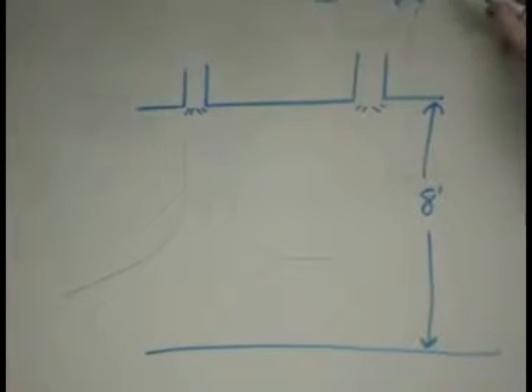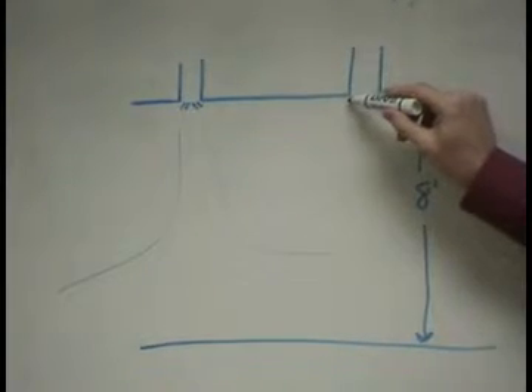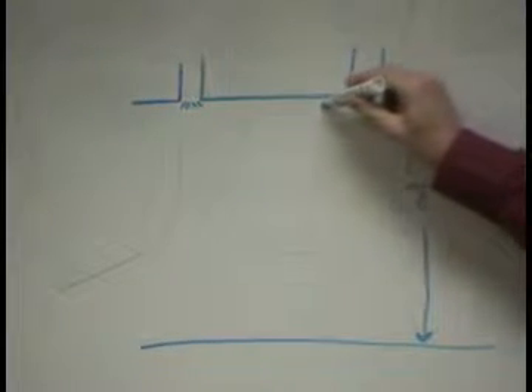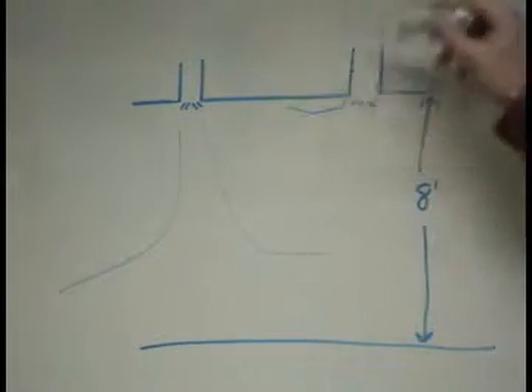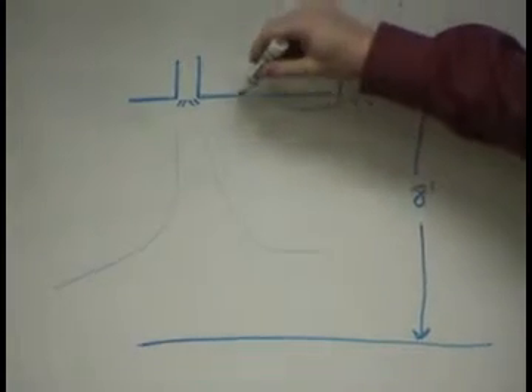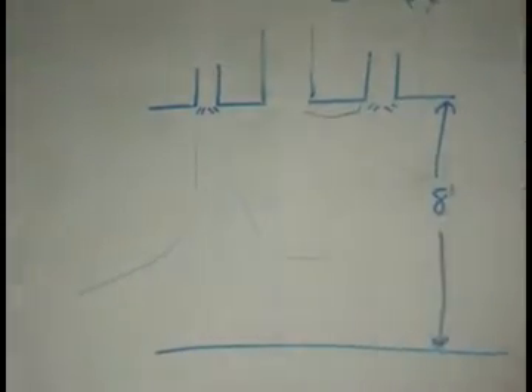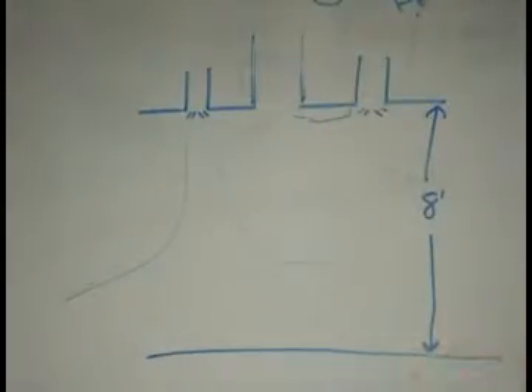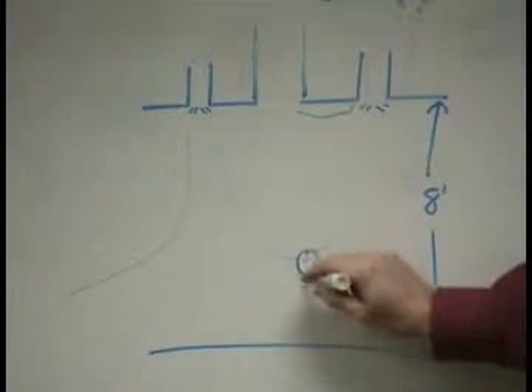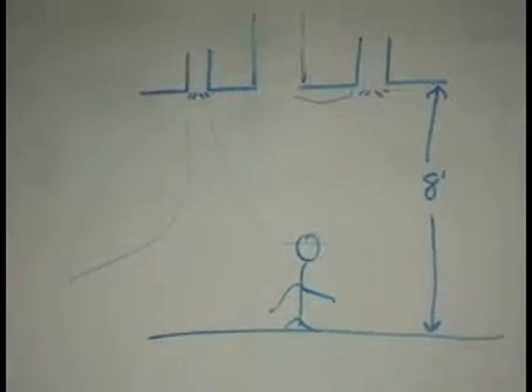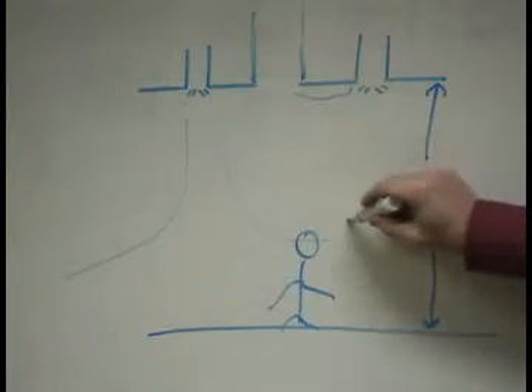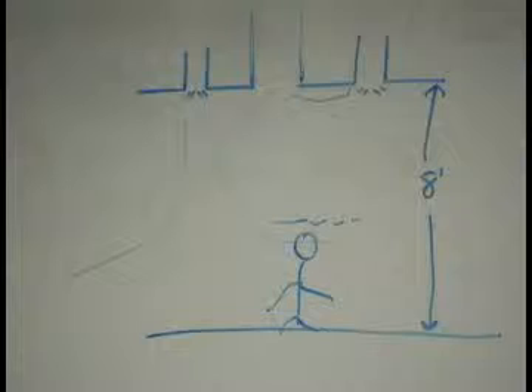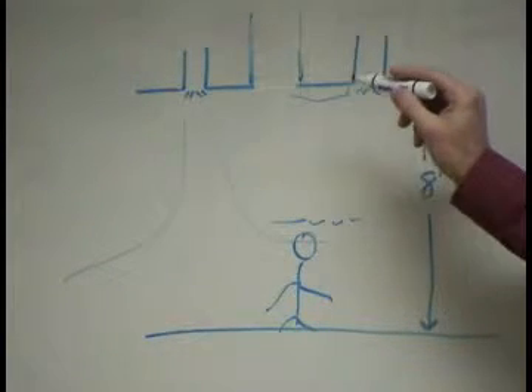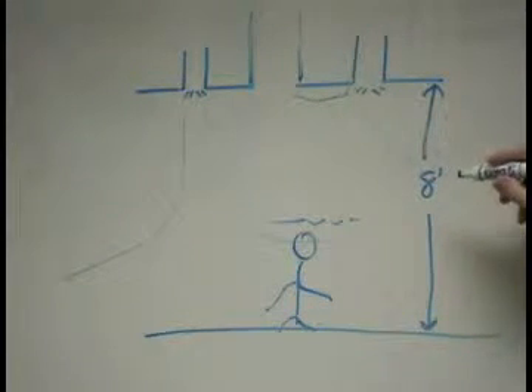Now I've got hot air at 400 CFM or 100 CFM coming out of here, and here's what I get. It comes out of here, it trickles along the ceiling, and since all the other ductwork was up in the ceiling, let's put the return up there too. We'll have our return duct here. You know, there's our egg crate over in the corner. So all this air comes out, trickles over, and sucks up into the return. Here's the occupant of the building sitting on a chair down here. Joe is sitting there at, you guys are probably sitting, your head height is probably about 4 foot off the ground right now. This heat is never going to see you. It is never going to get anywhere close.